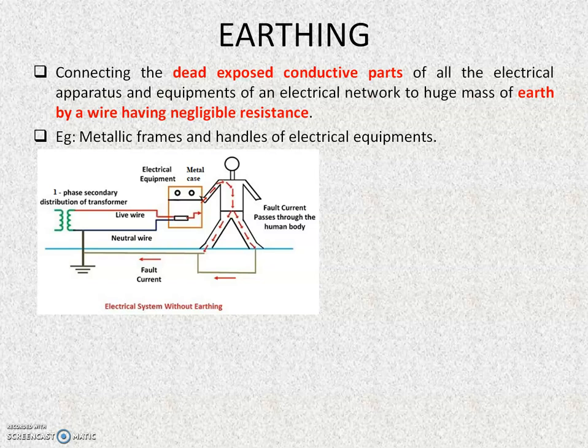So why are we connecting these exposed conductive parts to the earth? Let us discuss a case where there is no earthing. I am considering a case like this. I have an electrical equipment with a metallic case and it is connected to a supply with a live wire and a neutral wire. So there is a live and neutral conductor in place. The live wire supplies the current and the current returns to the neutral wire. That is the normal operation.